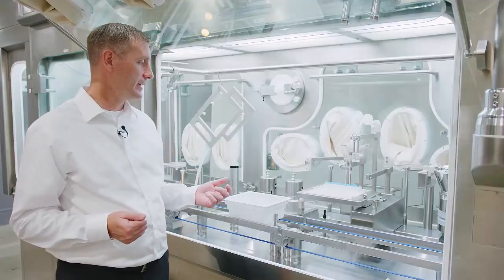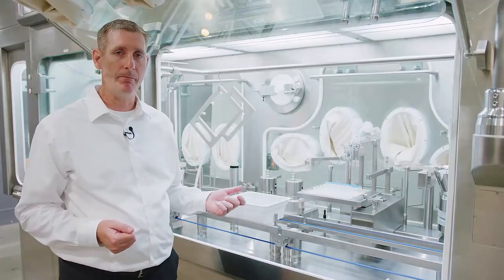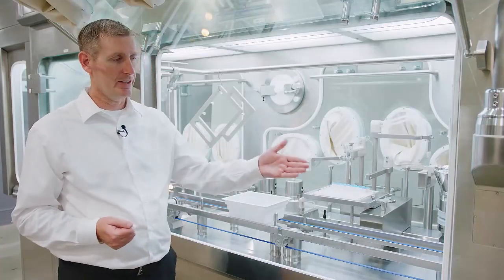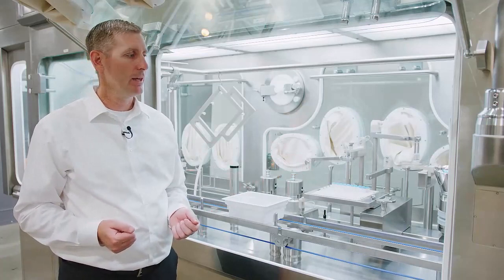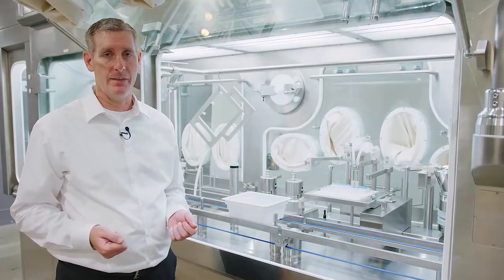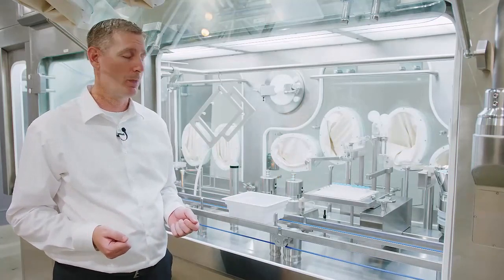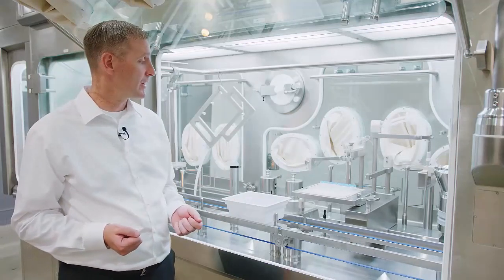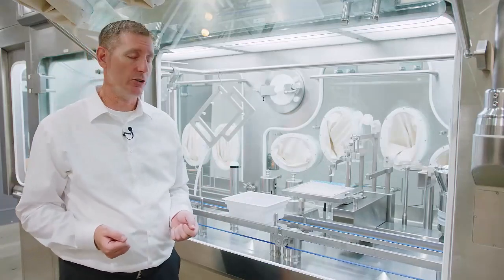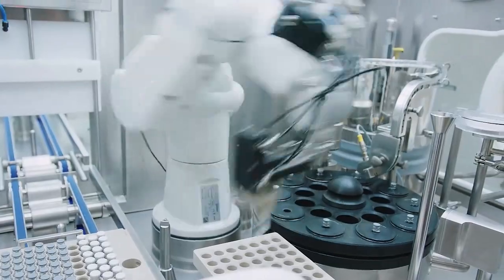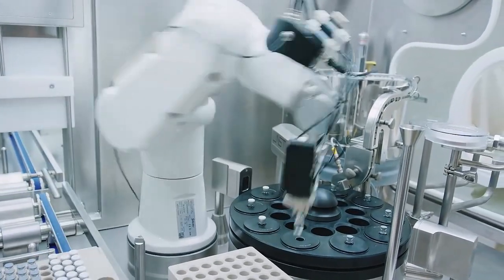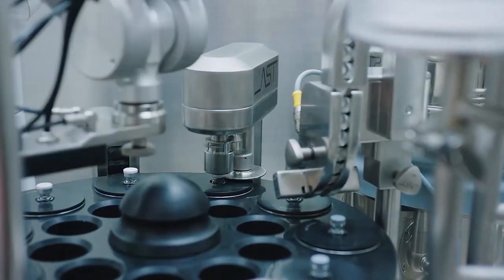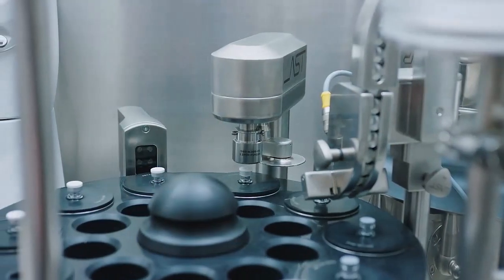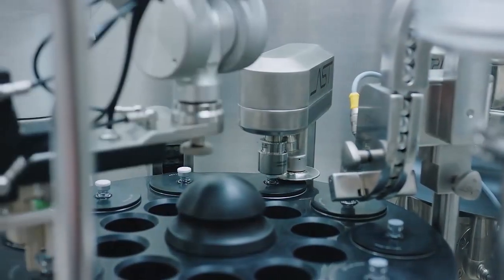So once the nest of vials is completed, the tub will exit from the aseptic isolator into the background clean room in this particular application using press fit caps. If it was an aluminum cap application, it would go to our vial sealing module, which is an additional module that is designed to apply the aluminum overseal on a vial in accordance with the strictest conditions of Annex 1.